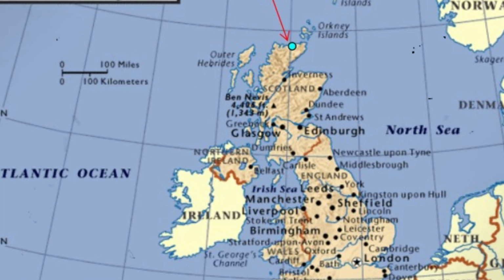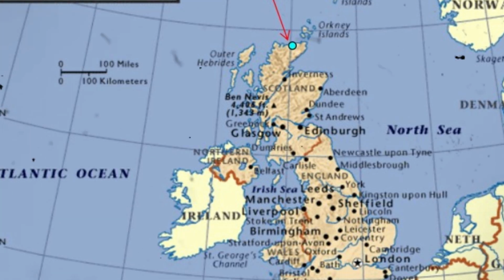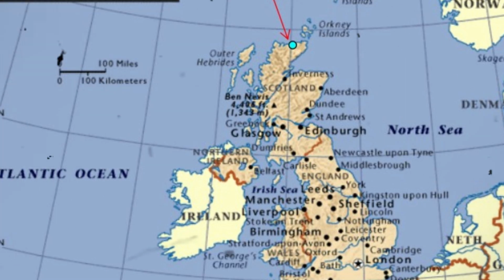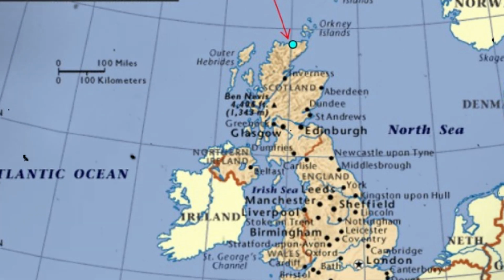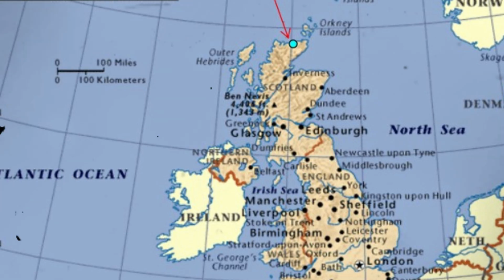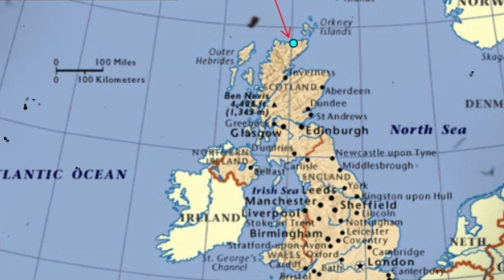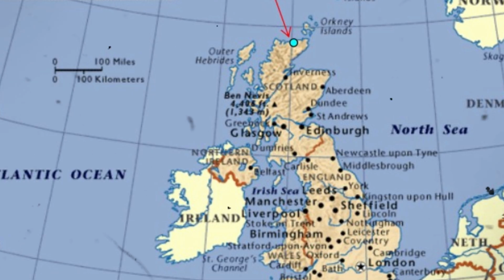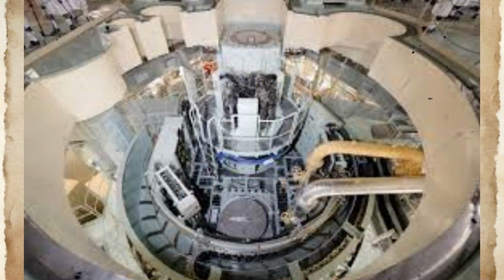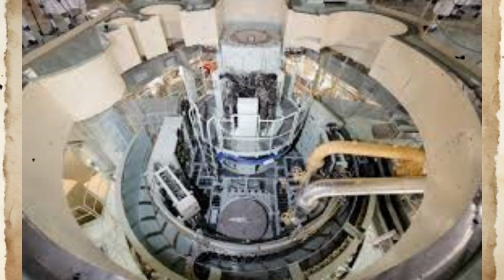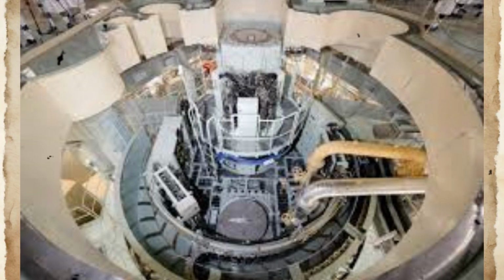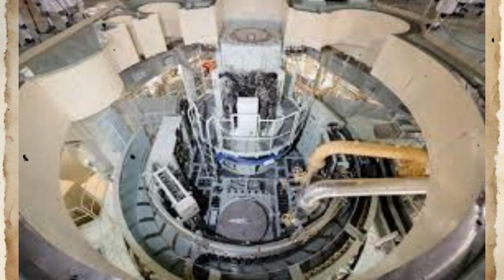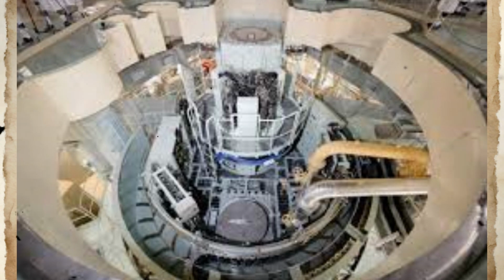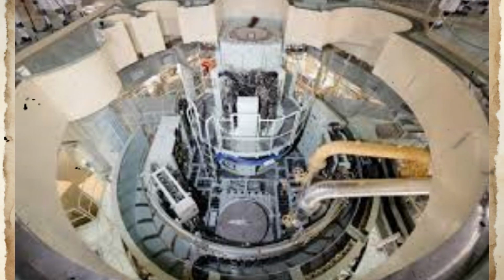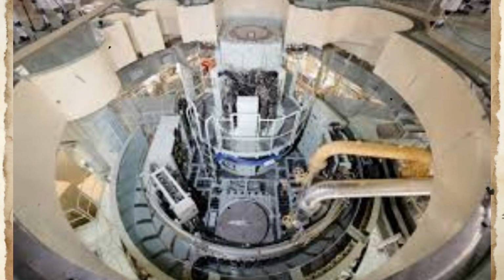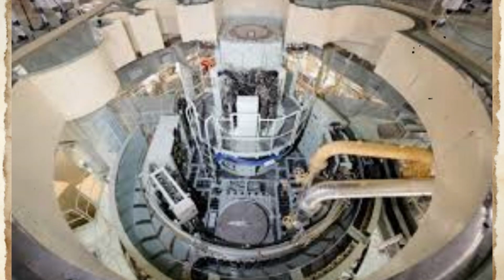The accumulation of sodium compounds on the piping room floor proceeded according to gravitational, settling, and chemical reaction kinetics. Sodium droplets ejected through the fracture opening followed ballistic trajectories determined by their initial velocity and gravitational acceleration. Upon impact with room surfaces, the sodium spread according to surface tension and wetting characteristics, then began oxidizing through contact with atmospheric components. Post-incident examination revealed that approximately 1 cubic meter of solid sodium compounds had accumulated in a semicircular pattern beneath the failed thermocouple well location.